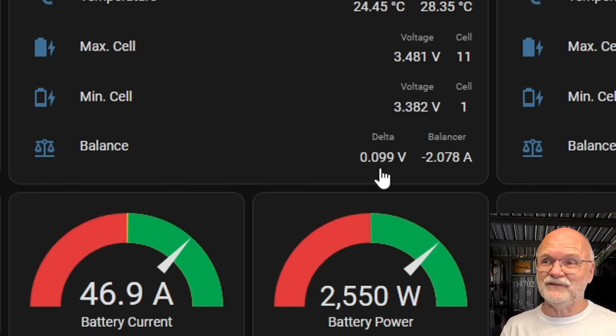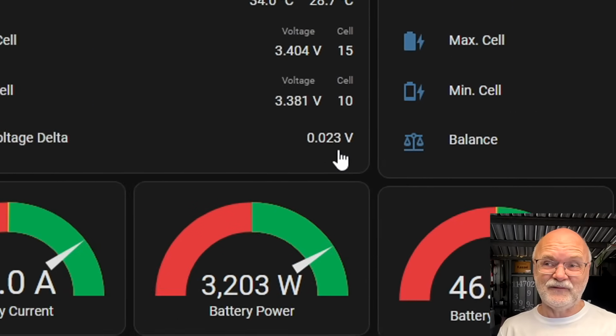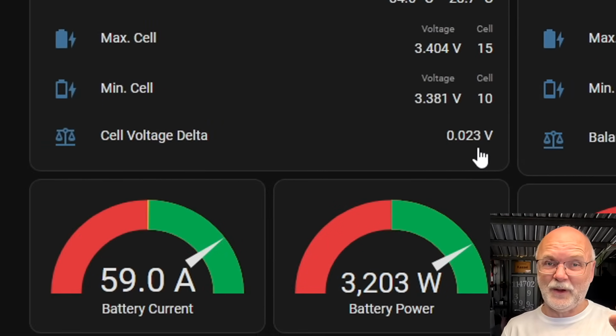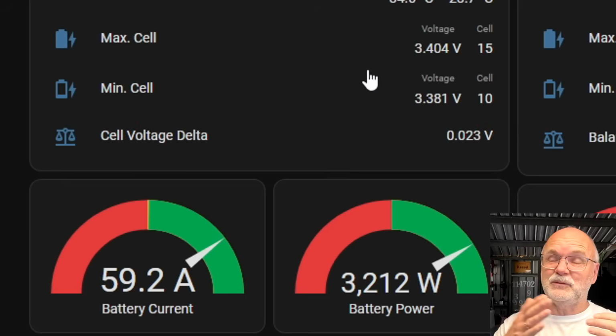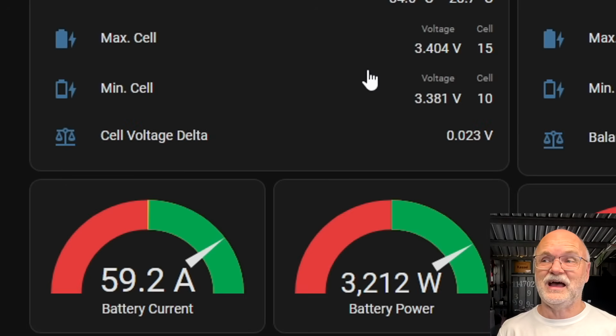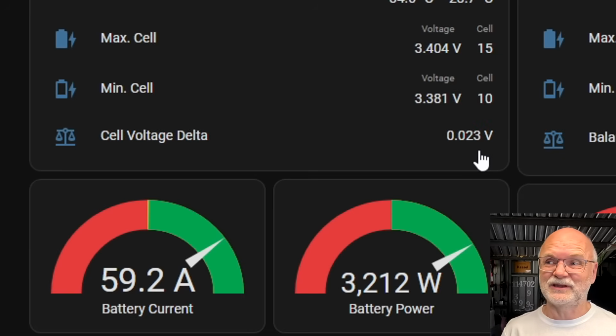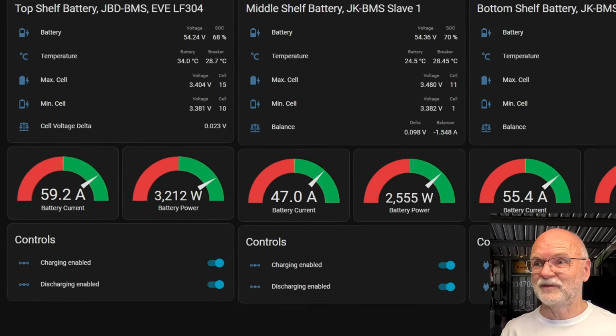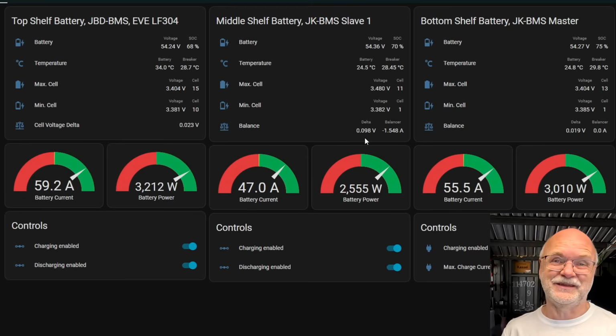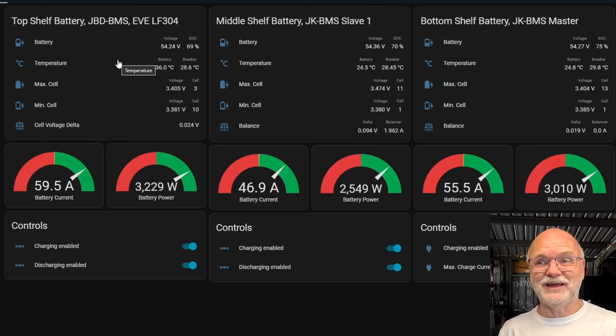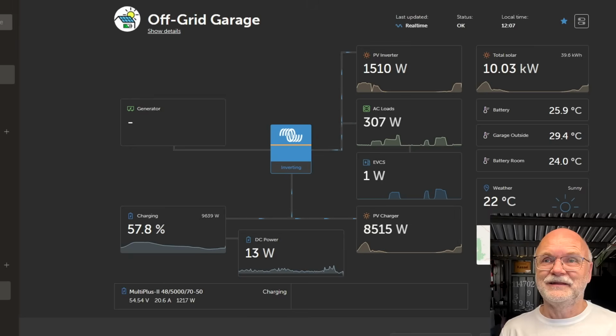These version 1 EVE cells had really bad terminals, the aluminium was not great. Yeah, these cells have aluminium terminals as well, but they're welded with a stud on it, and we're using the same tin copper bus bars for all 3 batteries now. We only have 20 millivolt deviation top and bottom, but 100 millivolt here in the middle shelf because of this oxidation layer. But anyway, we are charging along quite happily.